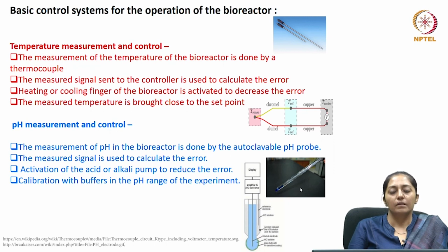For pH control, the measured signal is used to calculate the error. The activation of the acid or base pump is then carried out automatically to reduce this error. The pH probe requires calibration regularly with acid and alkali.